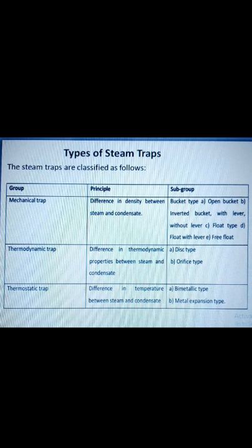There are three important functions of steam traps. First, discharge condensate as soon as it is formed. Second, have a negligible steam consumption, that means being energy efficient. Third, have the capability of discharging air and other non-condensable gases.